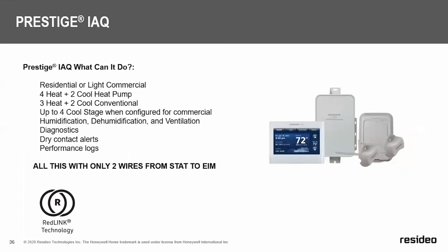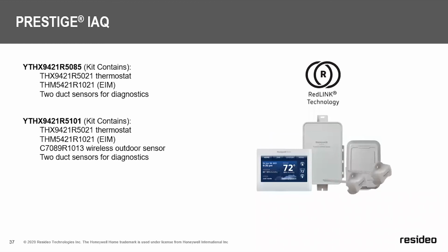Backing up the RedLINK Vision Pro is the Prestige IAQ, which is the good-looking older brother. Prestige IAQ is a 2-wire thermostat required for power at the thermostat head unit. Makes use of the equipment interface module all the time. It is residential or light commercial, 4 heat, 2 cool heat pump, 3 heat, 2 cool conventional. It offers the ability to control HUME, DEHUME, and ventilation, with the ability of adding diagnostics, dry contact alerts, and performance logs. Prestige IAQ is offered in 4 kits.